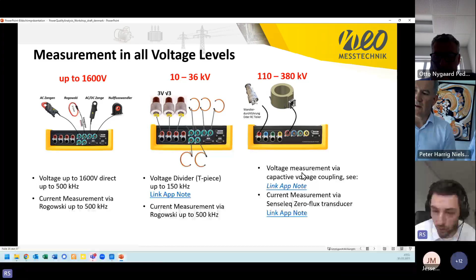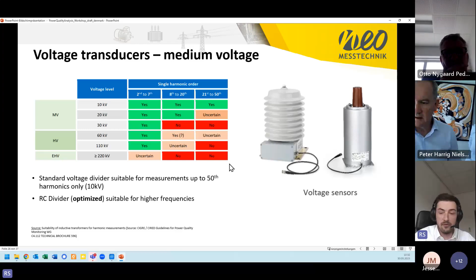If we talk about voltage transducers in medium voltage, and we look at the research done from the CIGRE guidelines, actually, we see that the standard voltage transducers are not usable, or only for 10 kV actually, are usable for the analysis up to the 50th harmonic. So what you actually need is, for example, an RC divider or optimized RC divider, which we are actually using for higher frequency analysis. So you need to be also in contact with the manufacturer if you look at this and if you compare this actually, so that you know that they are fulfilling the requirements to get these high frequency components also measured. And for the highest voltage level, we have then for sure a setup like voltage and current transducers.